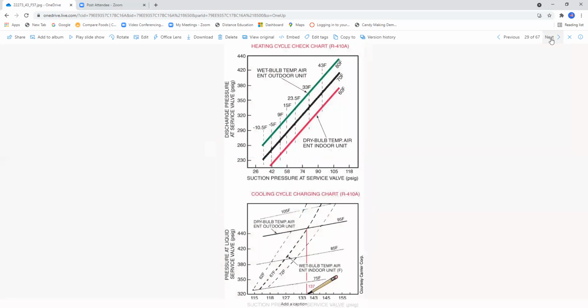Okay, this is a chart basically showing the suction pressure at the service valve in the heating mode and in the cooling mode. So basically this chart, I believe, is in your textbook. I know I saw it here somewhere. And I believe this is on page 1309, figure 43.57. Shows a performance chart for a 36,000 R410A heat pump system.